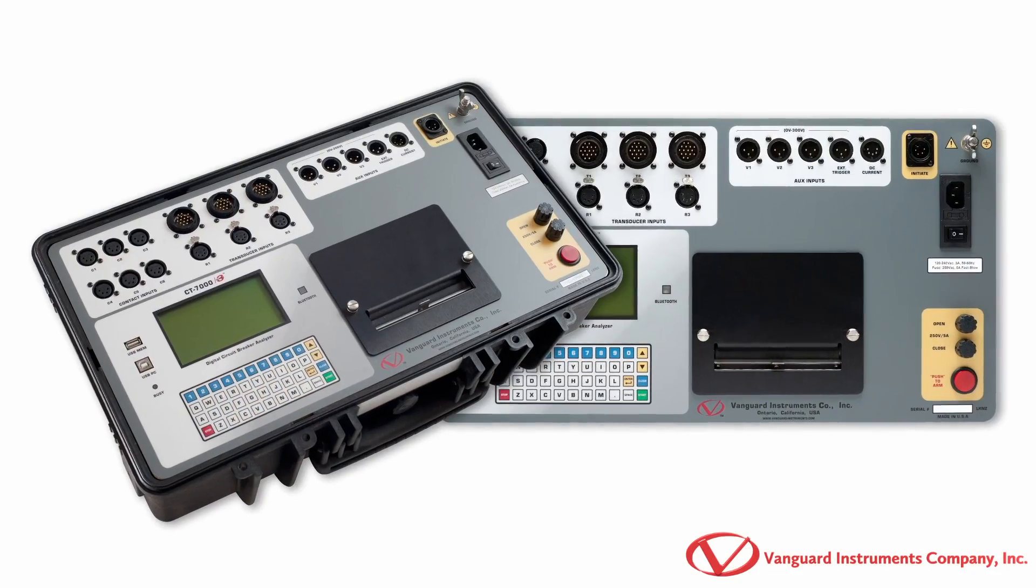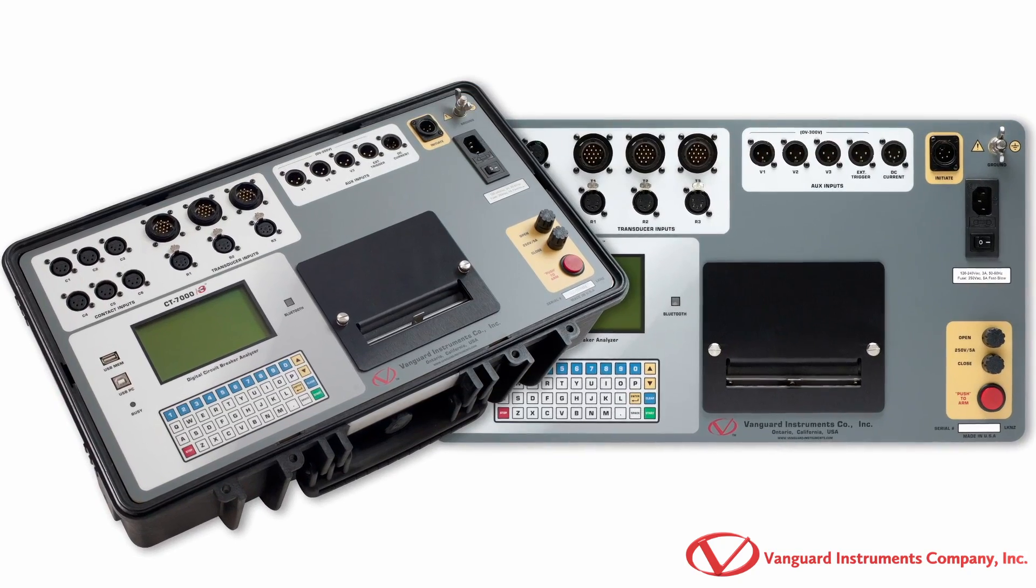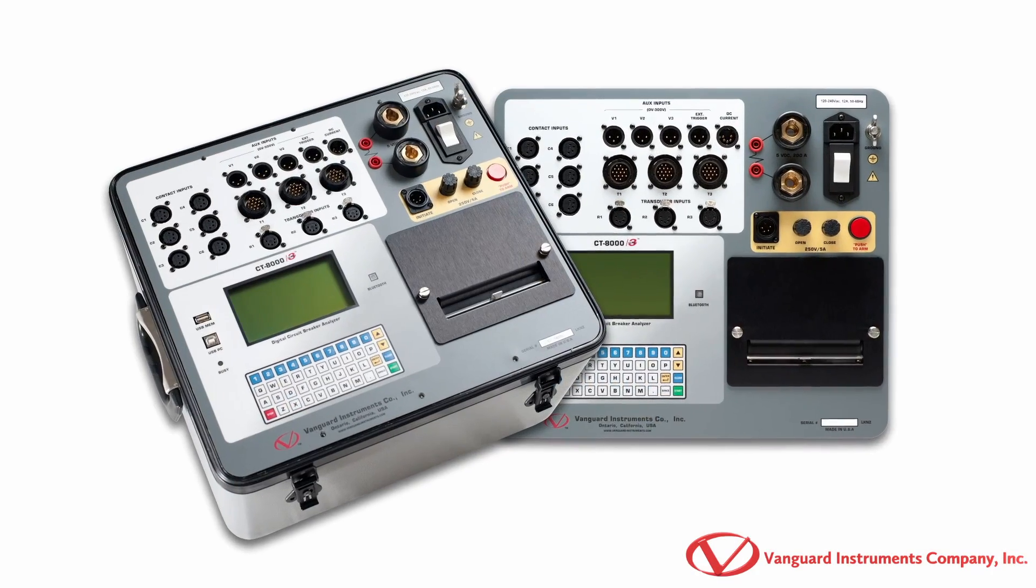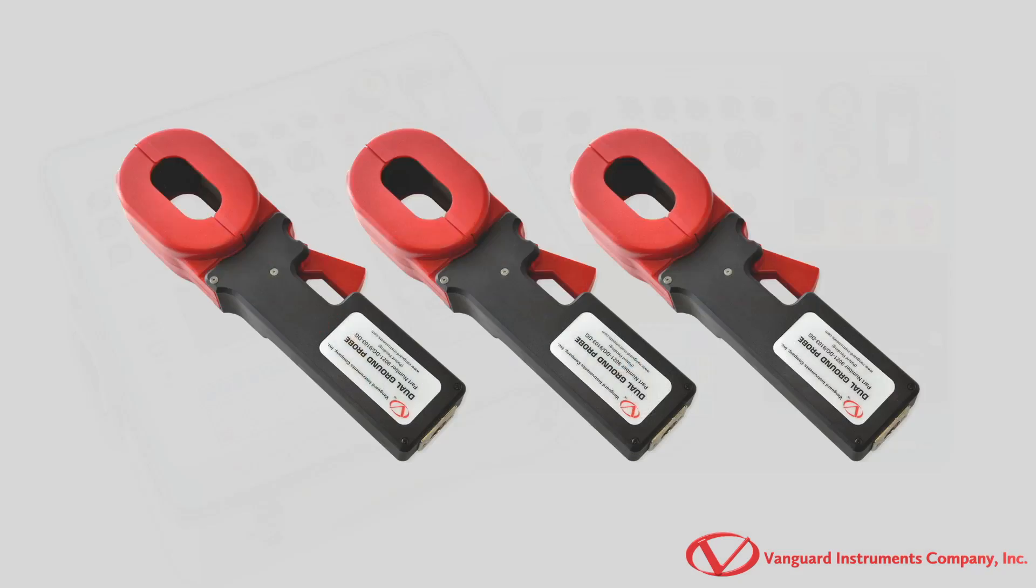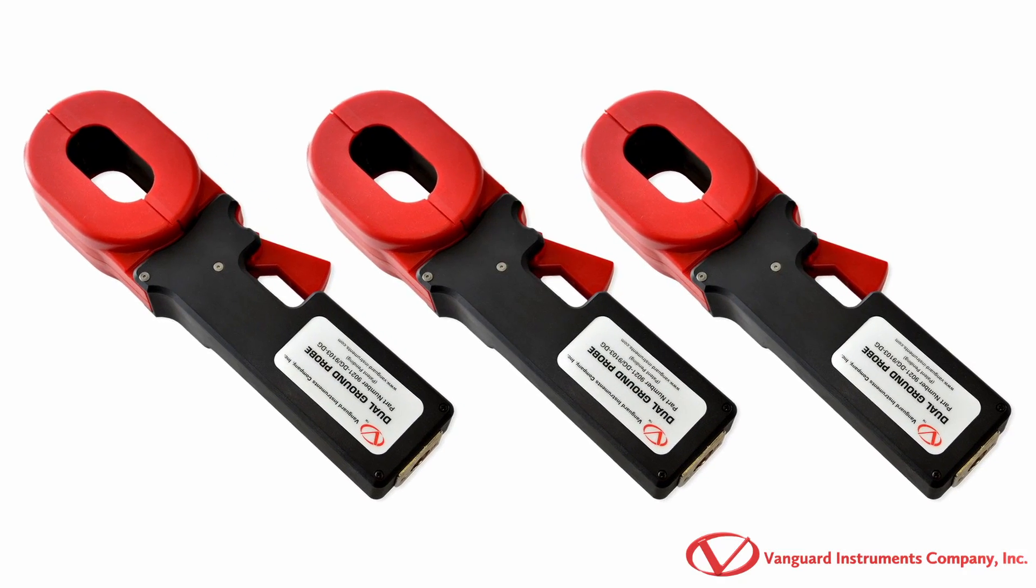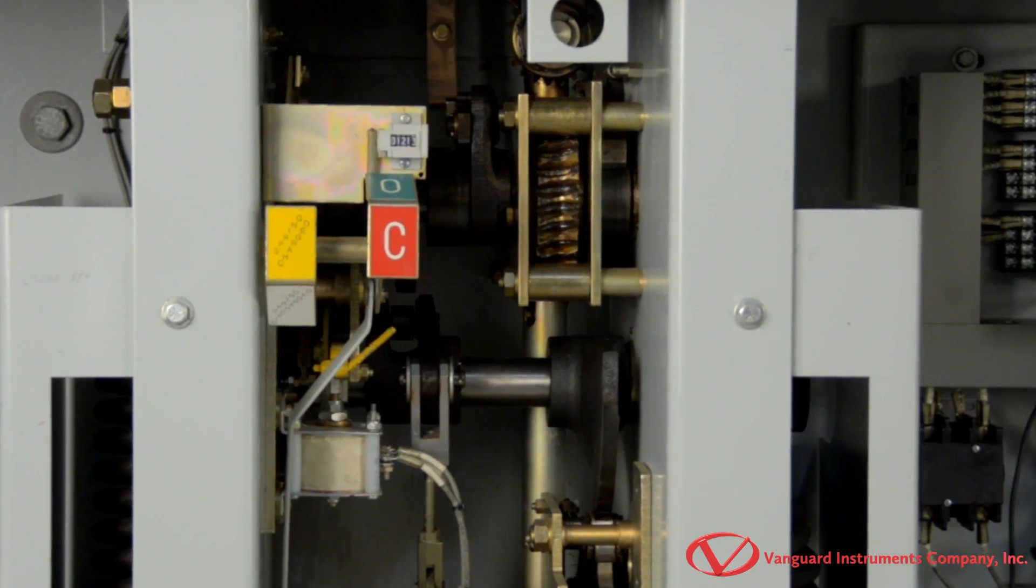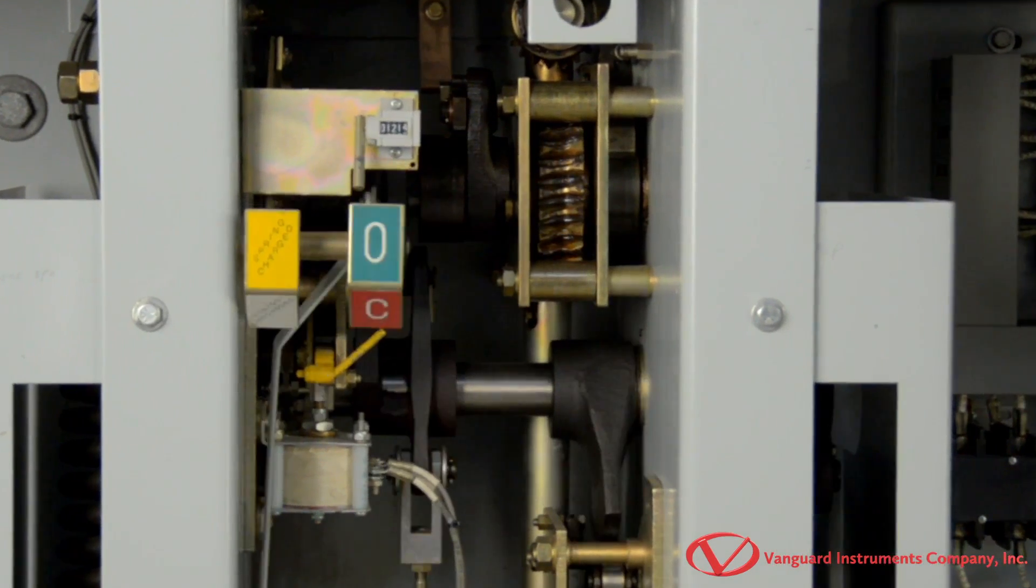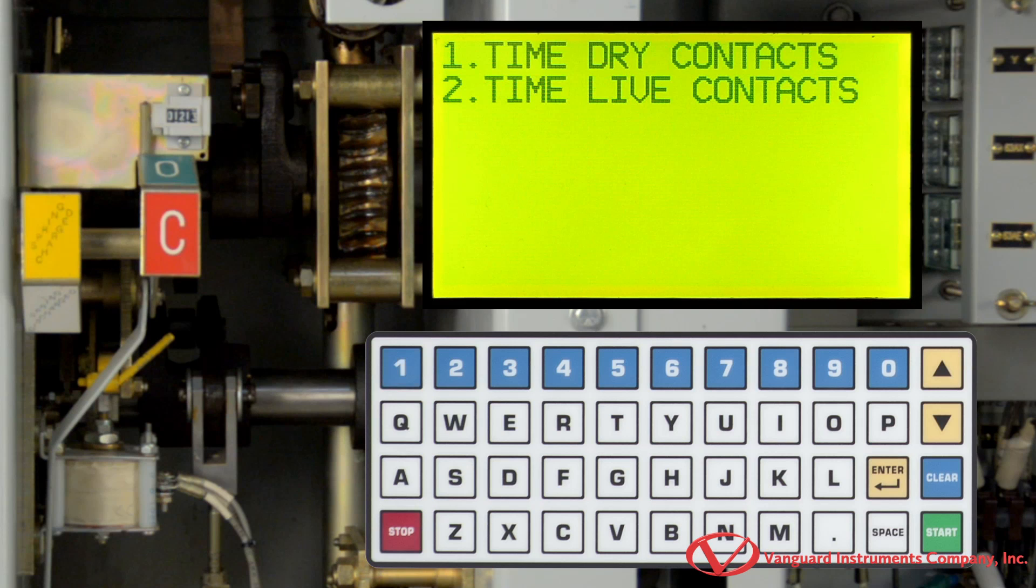The Vanguard Instruments state-of-the-art CT7000 S3 and CT8000 S3 circuit breaker analyzers offer a dual ground option for testing circuit breakers with both sides of the breaker grounded. With this option, users can safely perform tests with both sides grounded using the same procedures they are already familiar with for performing traditional tests.